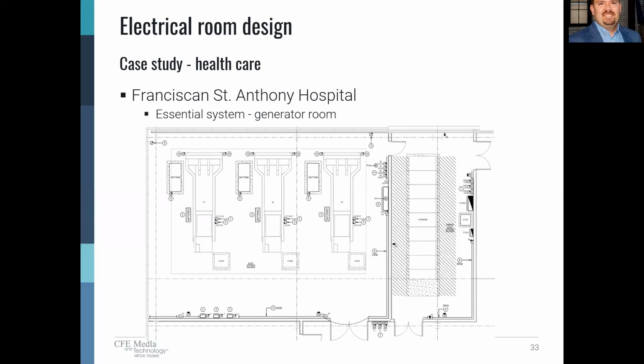Another aspect of the project that I'd like to highlight is the generator room. So this generator room has three 1.5 megawatt generators. You can see we've accommodated, so these generators are fed from buried fuel tanks outdoors. So the only fuel storage that we have interior to the building are the day tanks. So we more than adequately meet the 660 gallon fuel limit interior to the building. And you can see that we've got adequate working clearances around the paralleling gear that's located in the adjacent room with both front and rear access.